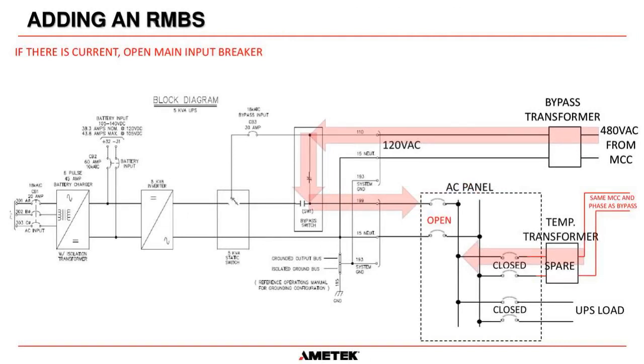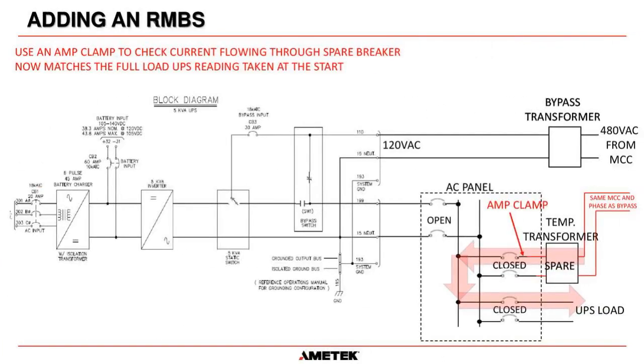So we've done all of our checks. We've seen that there is current. So we can open the main AC input breaker to the AC panel, because we've checked that there was current. As soon as you do that, once again, we take an amp clamp and go on here. If anybody was paying attention earlier, remember we said there was 20 amps going through the main breaker. So now we should have 20 amps going through this breaker.